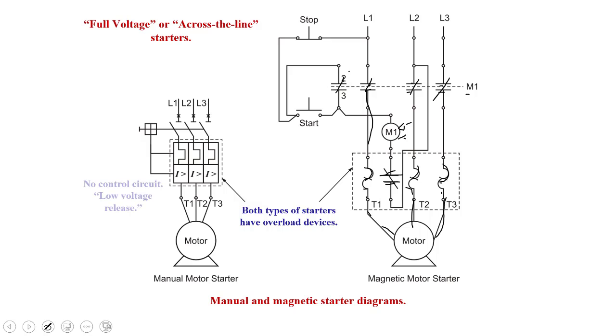So when we talk about these two types of starting mechanisms, the manual one doesn't have a control circuit. We could have the magnetic motor starter wired up as low voltage release too, as long as I used a maintained contact. But it's got low voltage release. So what's low voltage release? Well, if the power goes out to this circuit, the motor will stop running. And when power comes back on, it's going to automatically restore, and the motor will keep going.